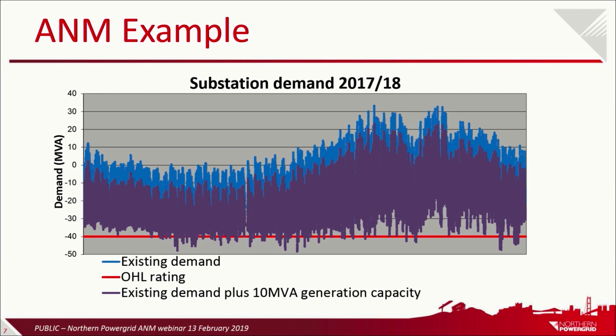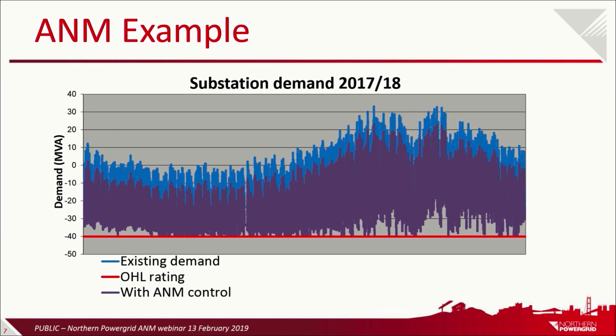In this next change, watch the bottom of the graph - you'll see the ANM scheme effectively stops the generator exporting at critical times, throttling it back, to make sure the power flow in the overhead line stays below that 40 MVA limit, keeping things within rating on the network.